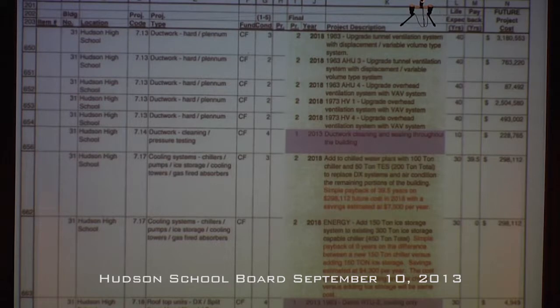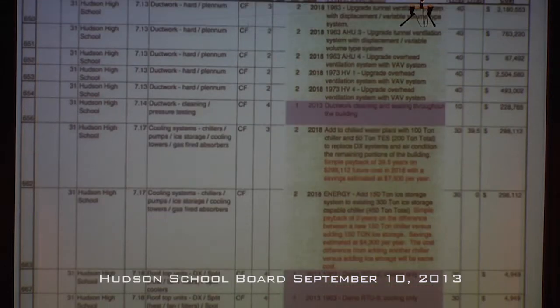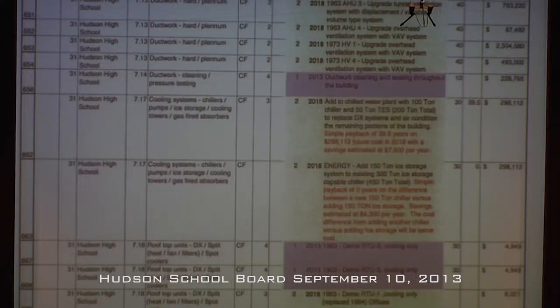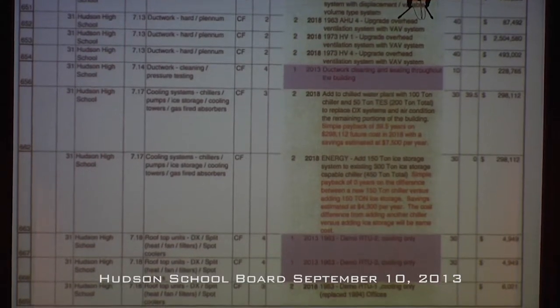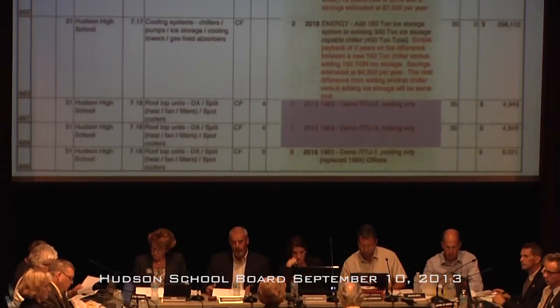We'd also like to add to your chilled water plant an extra 100 tons of chiller and 200 tons of ice storage so that you can store energy at night and use it during the day when the demand gets high, when it's hottest. It's cheaper to make the ice at night and then harvest the cooling in the daytime. That would just cover your existing cooling system.